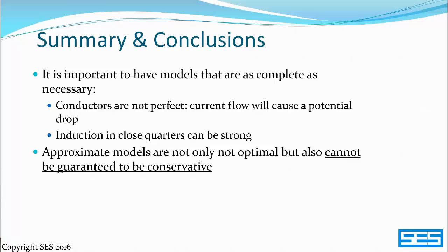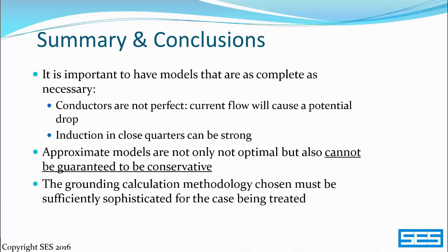There was a case we saw early in the presentation for which the equipotential assumption actually worked quite well, but it's important to ensure that the calculation methodology is sufficiently complete for the case at hand. Cutting corners could lead either to costly overdesign or an unsafe optimistic design.